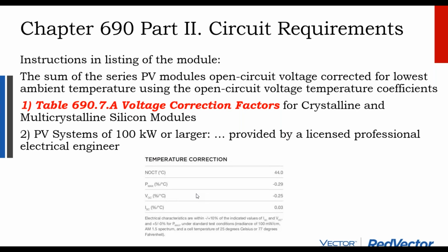And so if you are putting in a fuse on a solar circuit and you undersize the fuse by accident, it's most likely to blow in the summertime, because fuses are based off amperage and you will reach your maximum system amperage ever so slightly in the summertime. Whereas you'll get to your maximum system voltage in the wintertime when it's cold out.